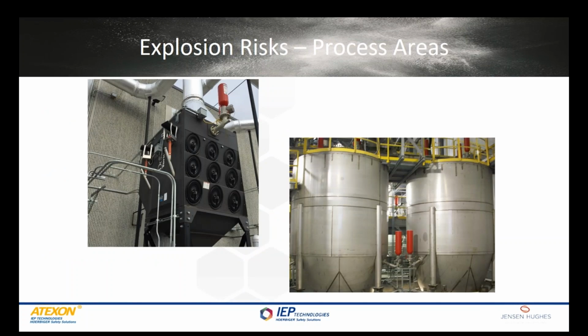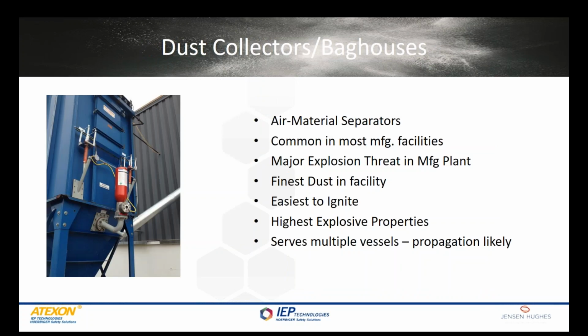I do want to quickly cover some of the more common explosion risks as far as process vessels within a biomass facility. Far and away, the one most commonly involved is the dust collector. In addition to the parameters that Martin had mentioned, the dust collector has the finest material within the entire plant. Think of that fine material as comparing a log versus kindling: the finer the dust, the easier it is to ignite, meaning the least amount of ignition energy is necessary to start a deflagration. In addition, the finer the dust, the more severe the explosion properties are going to be. The faster the rate of pressure development, the higher the KST, the higher the Pmax, the easier it is to ignite.